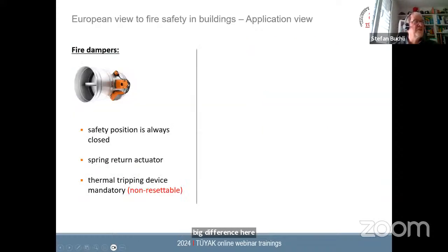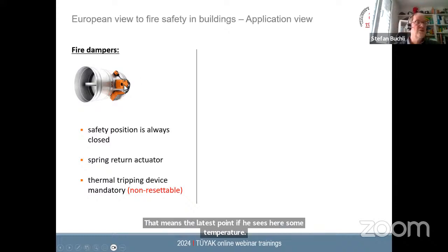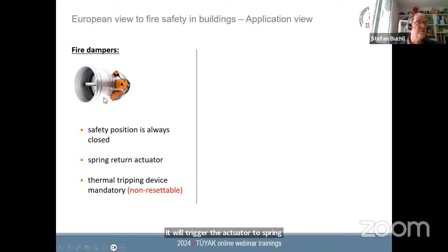A little bit closer look at fire dampers. As I said, the safety position is always closed. The spring return actuator is not a standard spring return actuator. It's a very dedicated design of actuator for fire dampers because it usually has some sort of thermoelectric tripping device, as you can see here on the damper. This is the primary safety element. That means at the latest, if it sees a certain temperature, it will trigger the actuator to spring return the damper to the closed position.